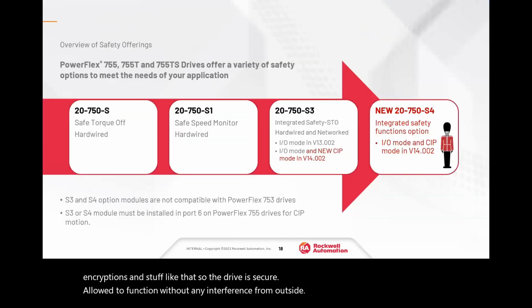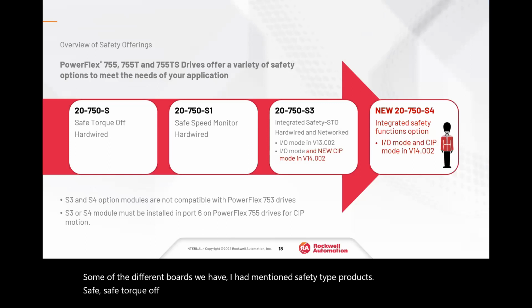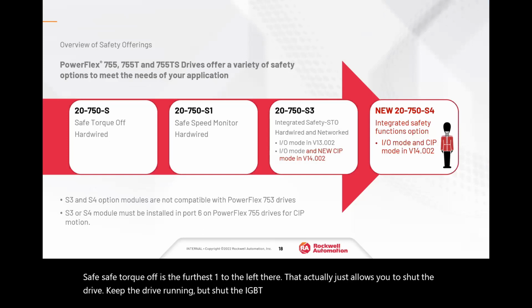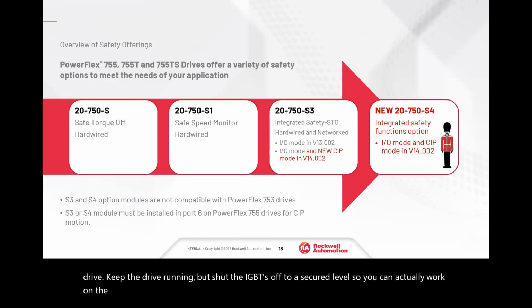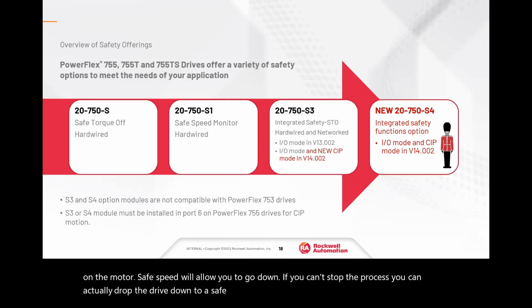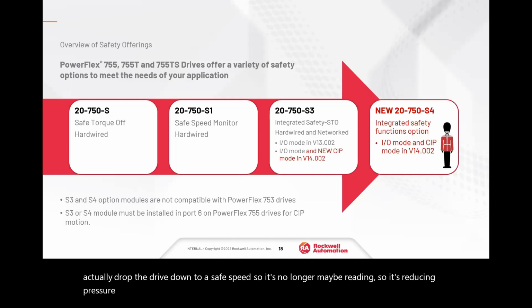Some of the different boards we have, I had mentioned safety type products. Safe torque off is the furthest one to the left there. That actually just allows you to keep the drive running, but shut the IGBTs off to a secured level so you can actually work on the motor. Safe speed will allow you to go down. If you can't stop a process, you can actually drop the drive down to a safe speed, so it's reducing pressure or reducing something to keep the process flowing or moving.